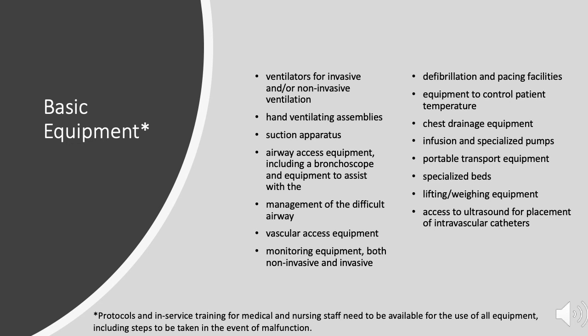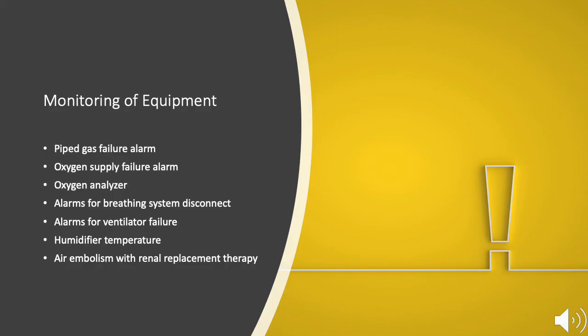Critical care also involves specialized equipment, including mechanical ventilators, defibrillation devices, vascular access equipment, and many other essential tools. Protocols and in-service training must be provided for medical and nursing staff on all equipment. To ensure patient and staff safety, monitoring of equipment for malfunction must also occur. Common equipment monitors include piped gas failure alarms, oxygen supply failure alarms, oxygen analyzers, alarms for breathing system disconnect, alarms for ventilator failure, humidifier temperature alarms, and air embolism detection with renal replacement therapy.